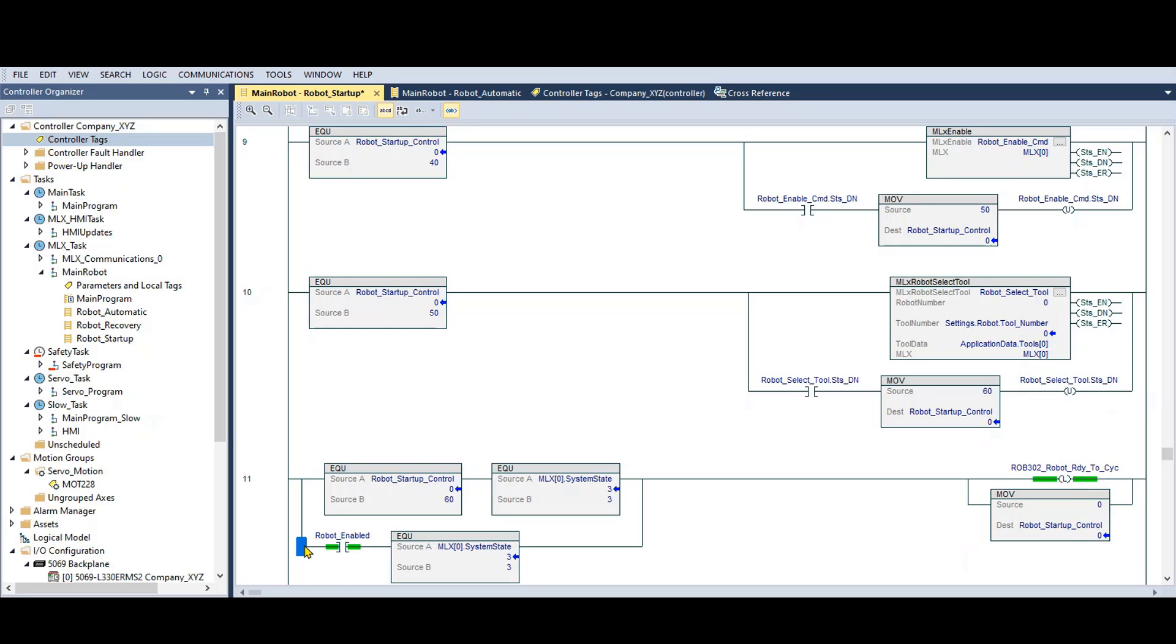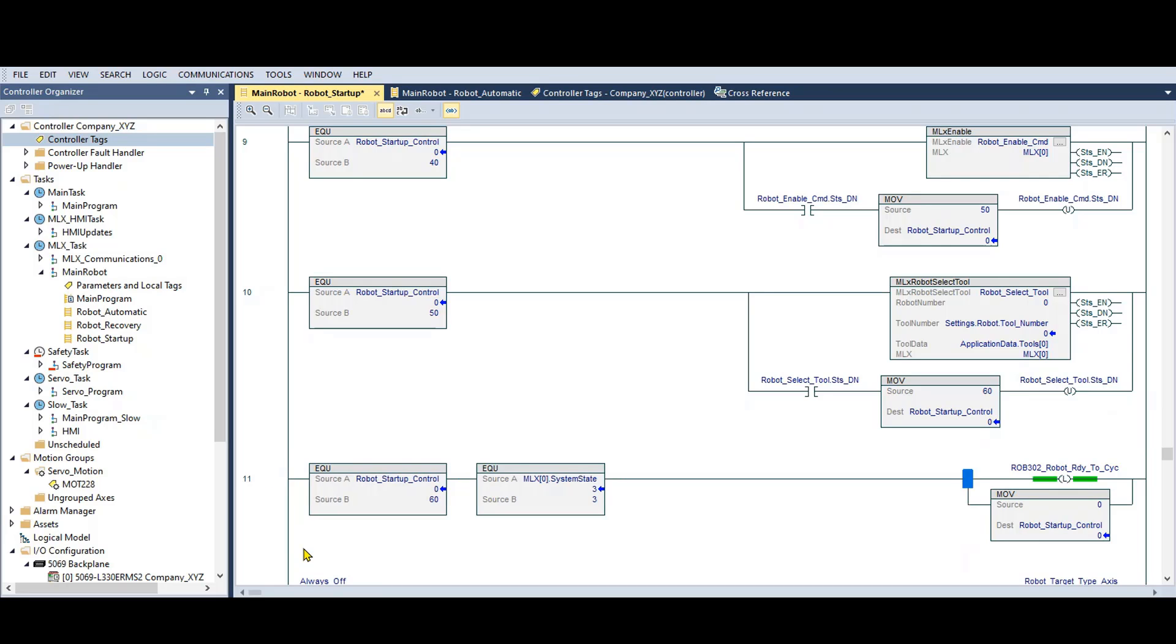So the solution to this lockup is to delete this branch and make it wait for startup step number 60.